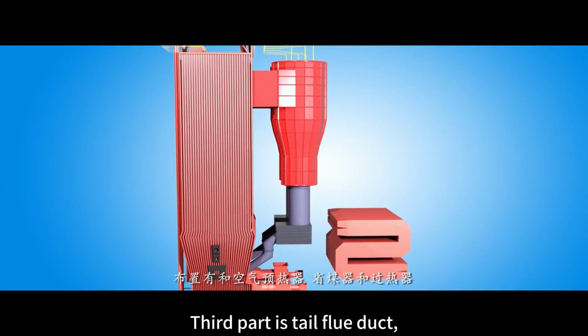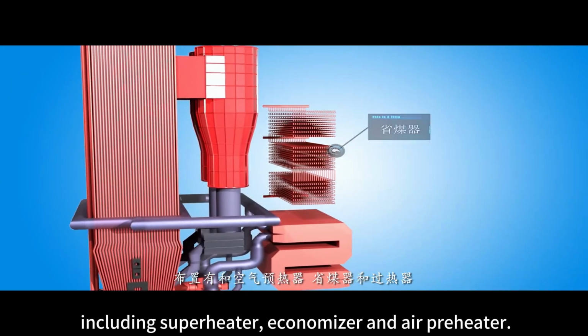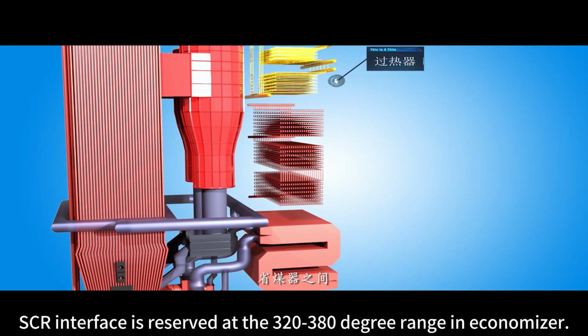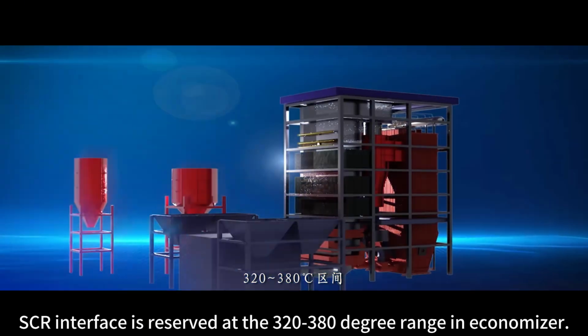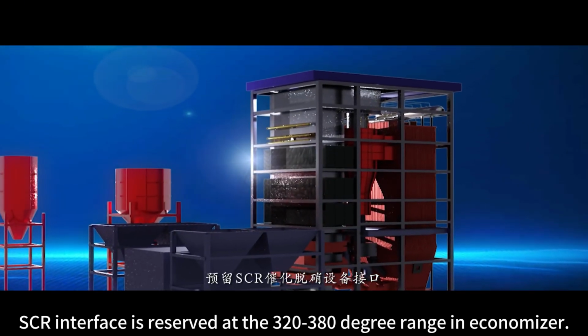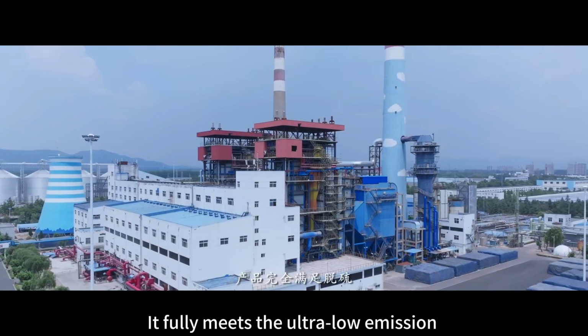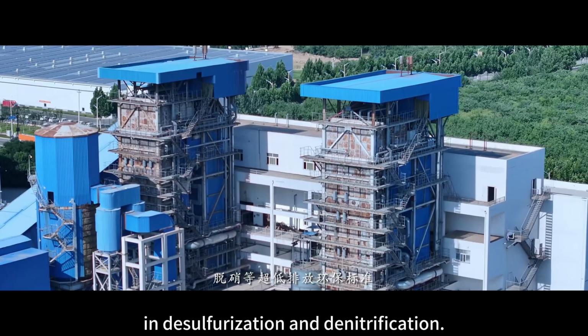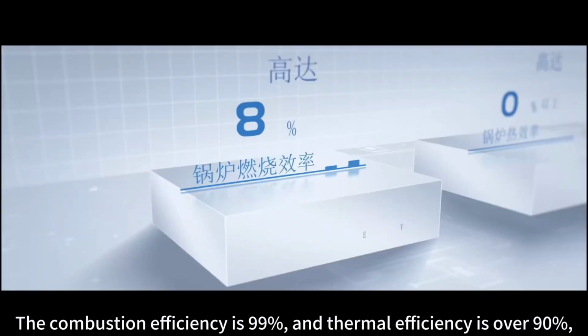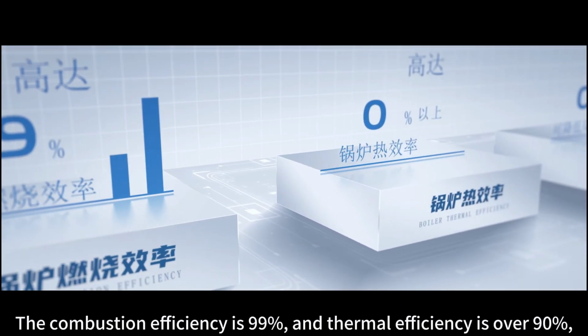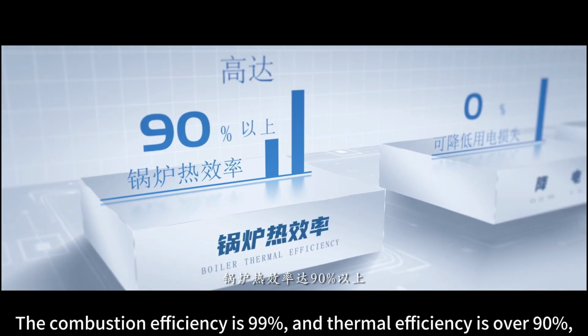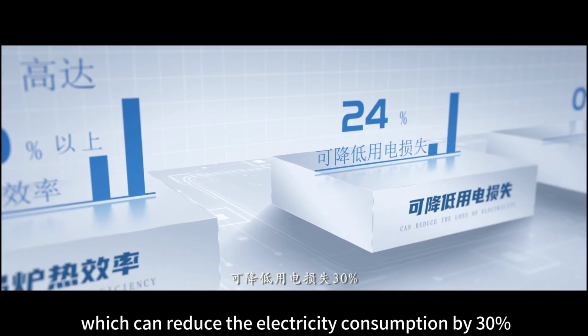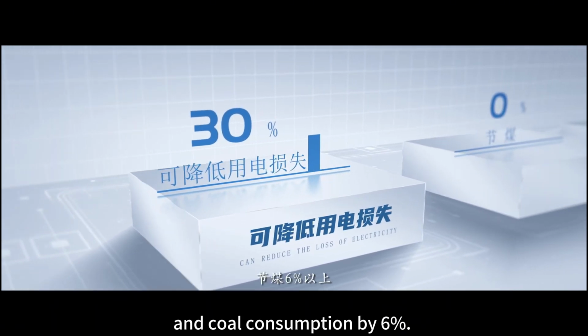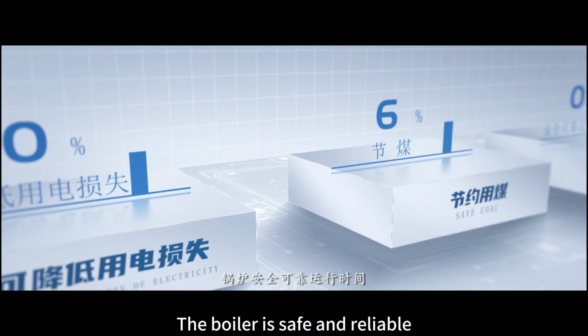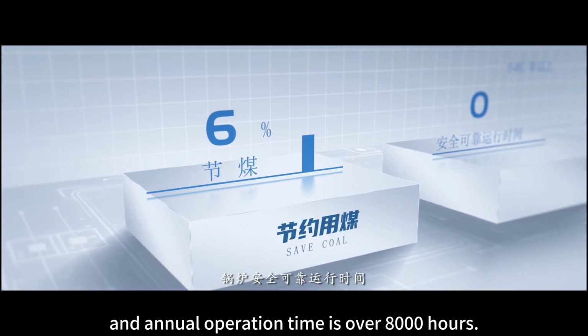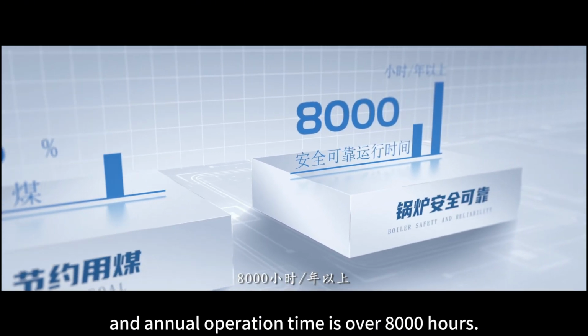Third part is tail flue duct, including superheater, economizer, and air preheater. SCR interface is reserved at the 320 to 380 degree range in economizer. It fully meets the ultra-low emission in desulfurization and denitrification. The combustion efficiency is 99%, and thermal efficiency is over 90%, which can reduce the electricity consumption by 30%, and coal consumption by 6%. The boiler is safe and reliable, and annual operation time is over 8,000 hours.